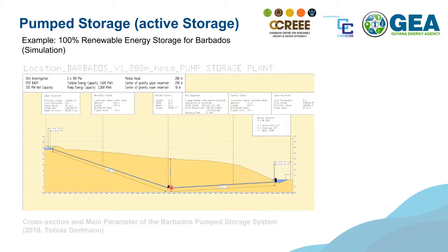So if you have large hydro pump storage plants, they can be 50-60 meters under the lower reservoir. The second point is that underground is very attractive because you don't have any land usage. You don't want a big power plant on the surface, but in this case it must be underground due to hydraulic reasons. So it's the cavitation on the pumps, that's the detailed answer.